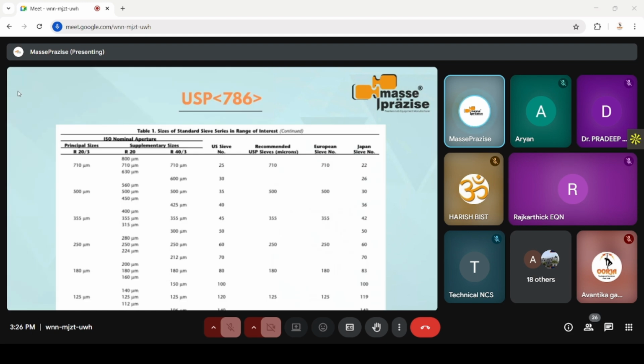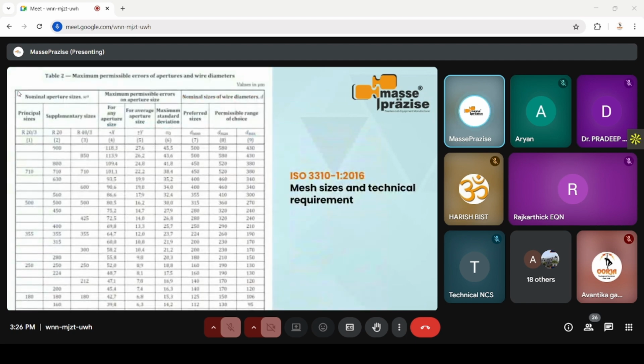Here is a screenshot of USP 786. This is just for reference. If you see, the data in USP 786 is identical to ISO 3310. Basically, USP 786 is derived from ISO 3310. ISO is the principal document. So as we see for 710 micron, the sizes are the same: 800 micron, 710 micron, 630 micron. These are supplementary sizes that may be possible in the range of 710 micron, and the recommended USP size is 710. So for a test sieve to be 710, we have to again check the data from the previous values, like in ISO 3310, and if the sieve complies with this data, then we may use this sieve for our process.